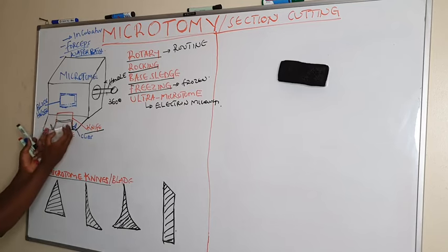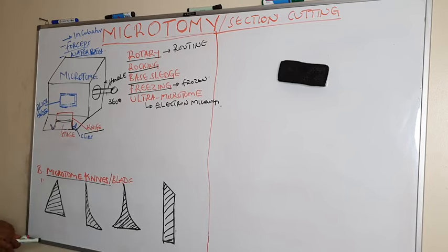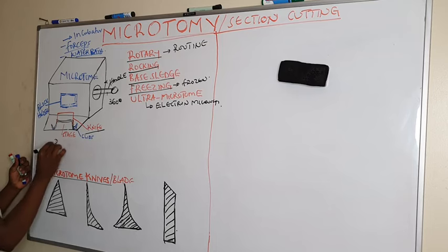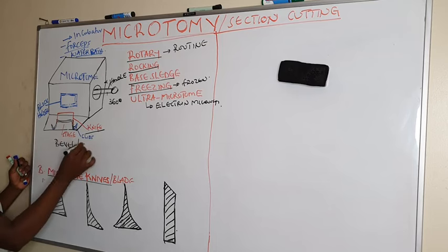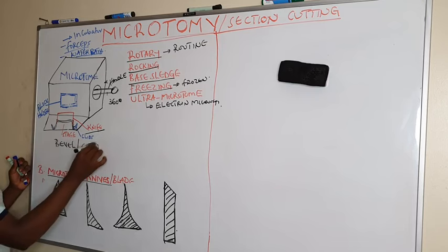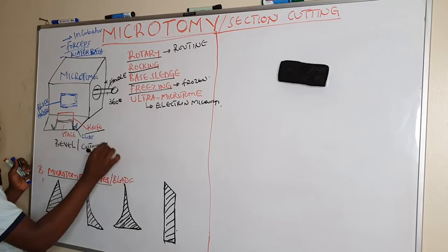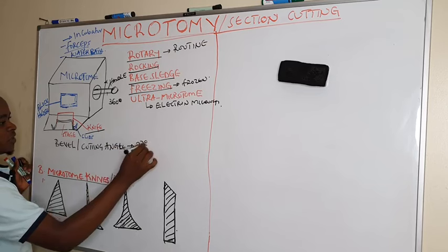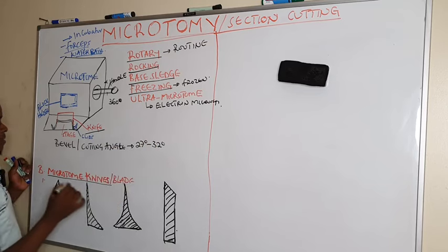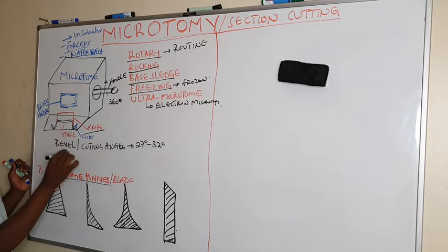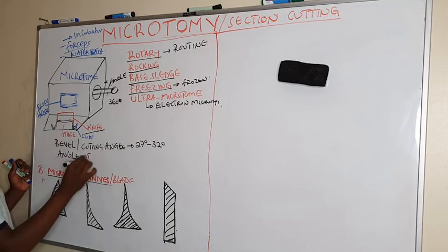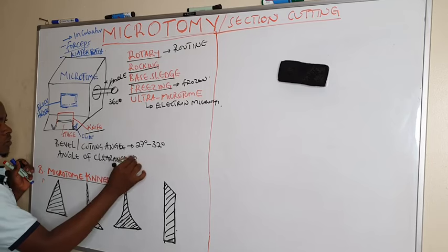When adjusting or fitting the knife on the stage, there are angle terms we use. The bevel angle, also called the cutting angle or facet angle, is always between 27 degrees to 32 degrees. The angle of clearance is always between 2 to 5 degrees.